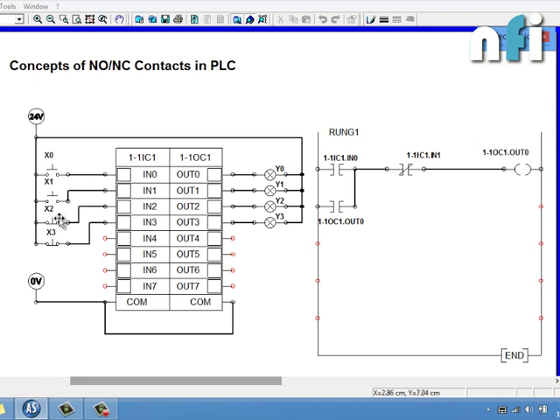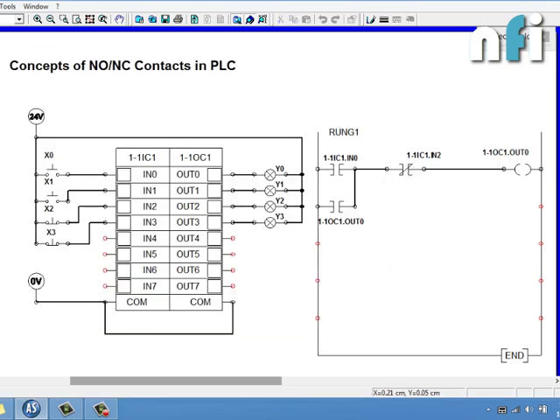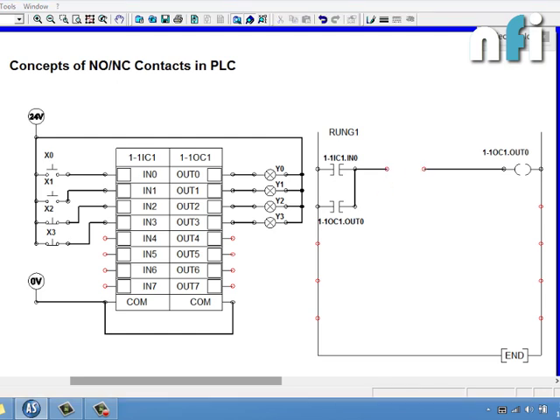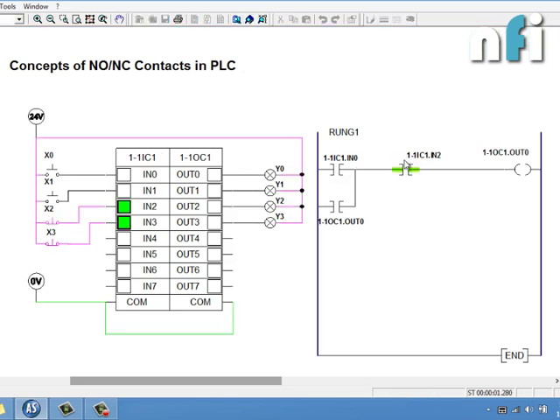Now I want the stop operation done by an NC switch — X2. For that, I'll take the NC contact of IN1 and rename it to IN2 as NC. This contact is already open because the relay is already on. Since the contact is open, I cannot turn on the output. So when using an NC switch to stop the process, you must take a NO contact inside, because the relay is already on and the NO contact will already be closed.